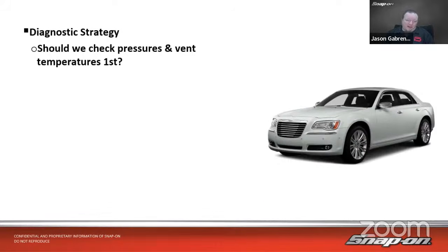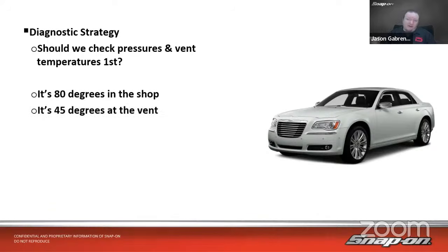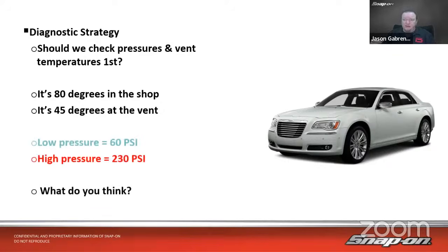So we need to figure out why this air conditioner is not blowing cold enough. First we need to verify the customer's complaint that it is in fact not blowing cold enough, and we should check the pressures too. So we'll check the pressures and the vent temperatures first. It's 80 degrees in the shop today, and it's 45 degrees at the vent. It's kind of close, but not 100% where we want it. The rule of thumb, from what I've been told, is about 40 degrees. If we can drop it by about 40 degrees from ambient, you're doing good.